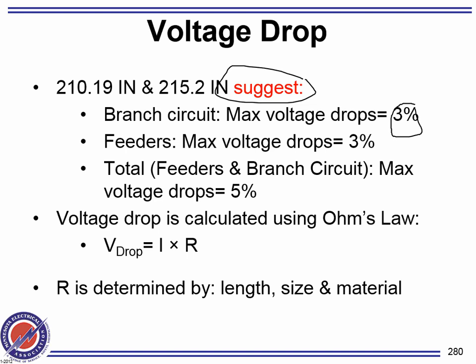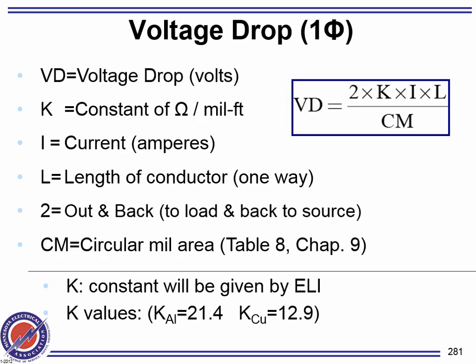On feeders, 3. Total feeders plus branch circuits is 5. So you can either have 2 and 3, or 3 and 2 for feeders and branch circuits. Right? You can't have more than 3 on any one of them. You can't have 3 and 3. Right? Or 4 and 1. You can't have more than 3. For all the calculations that we do, guys, on the test, you're allowed to use 3%. So you know.